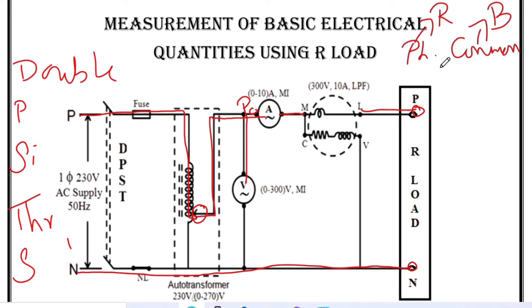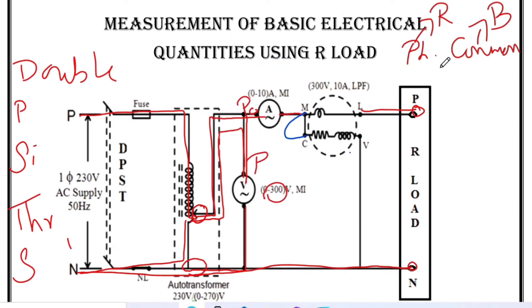The neutral of the load is directly connected to the neutral line. For the voltmeter connection, one end from the auto transformer is connected to the wattmeter's phase-phase terminal, which may be indicated in red color at the 300, 150, or 600 range. The common terminal is connected to the auto transformer neutral side, and the V connection at 300 volt is connected to the neutral of the load, completing the circuit. C and M terminals are connected externally with a short wire.